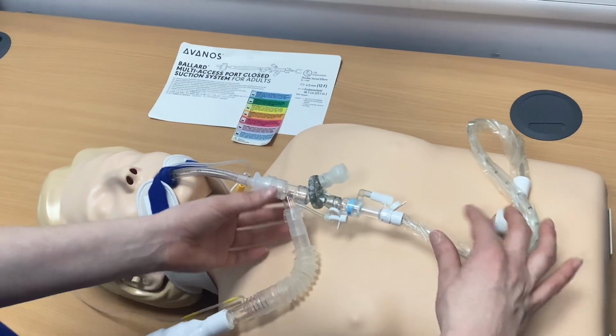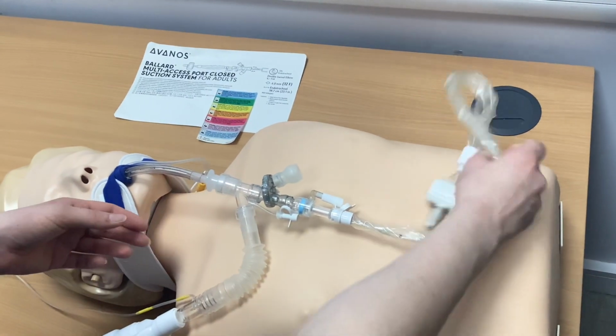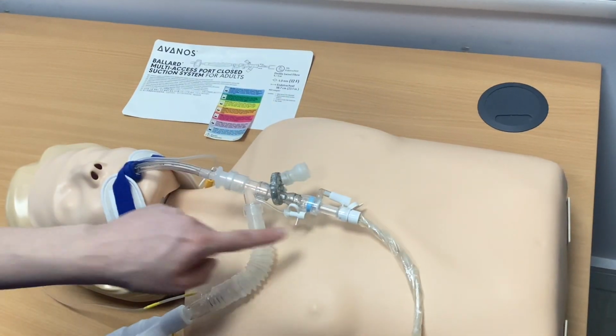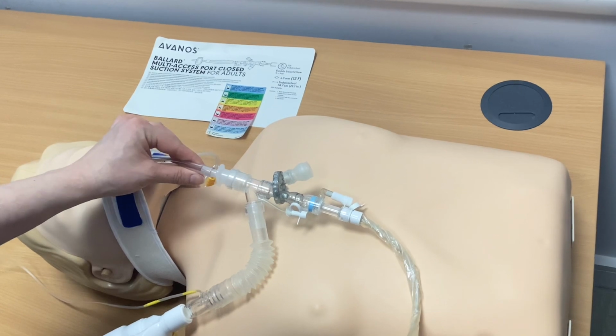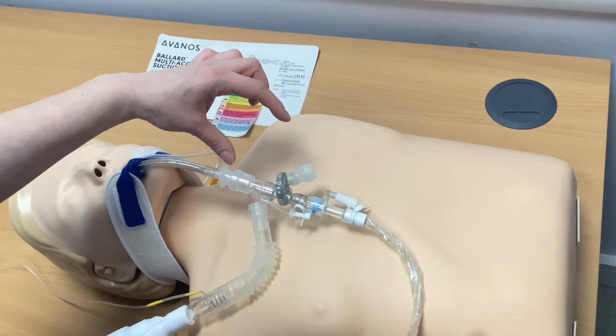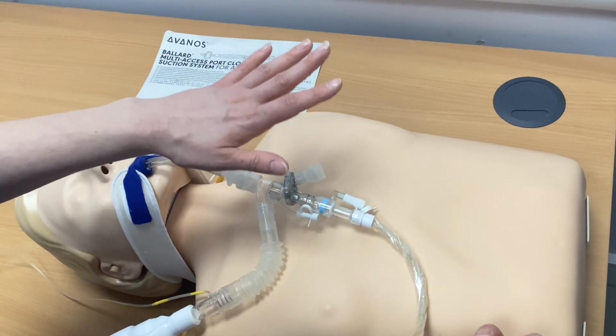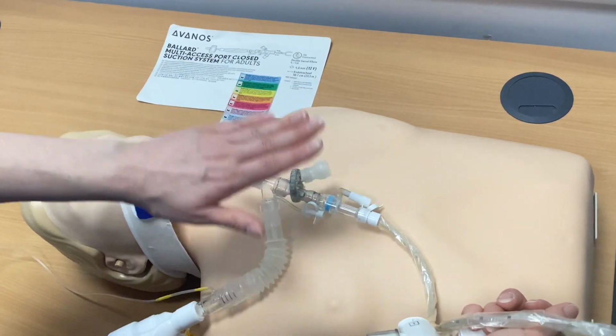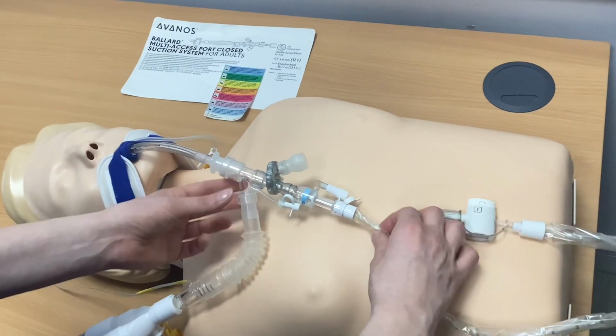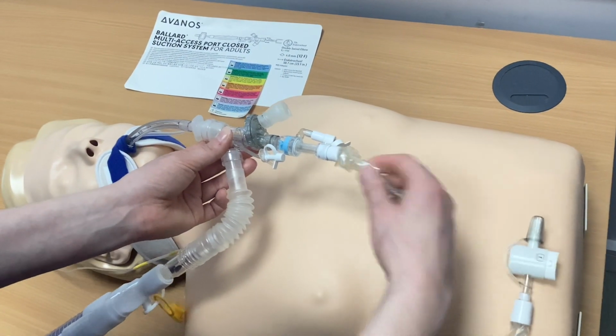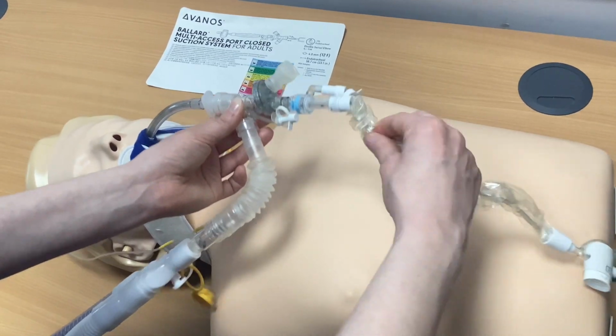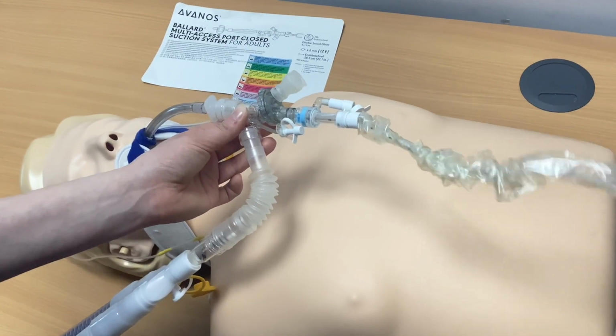On coming out of the pack, the multi-site will be in the inline suction position. The multi-site will also give access to a bronch port and a neutral position, which can be used to maintain PEEP when changing the suction catheter. So initially you're able to put your suction catheter down into your tube and suction your patient, like so.